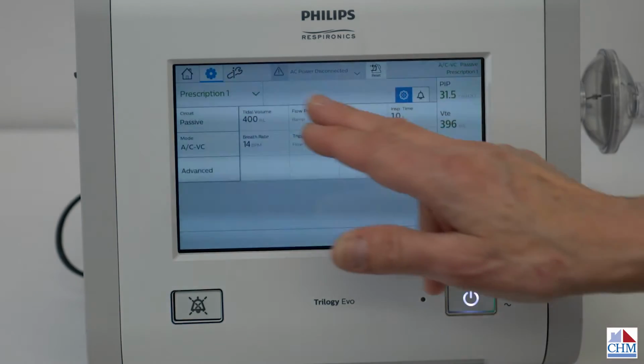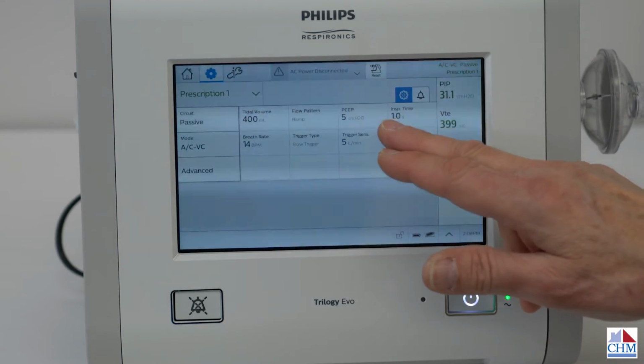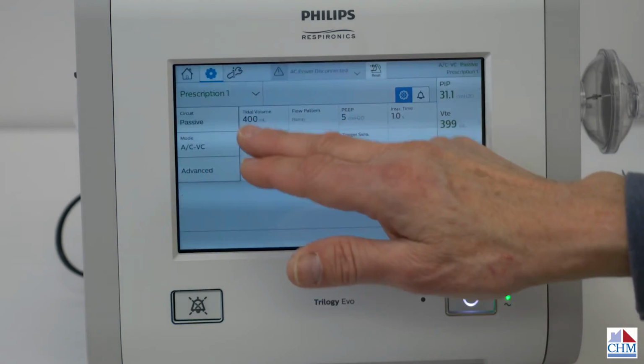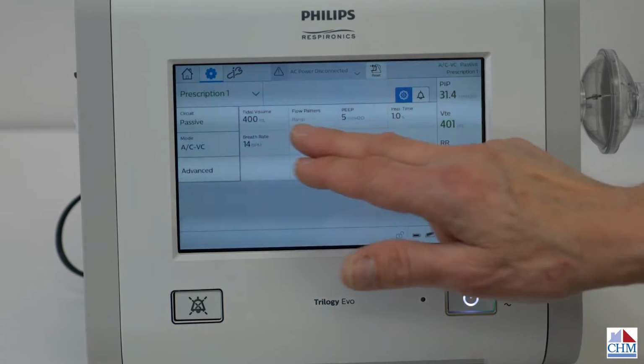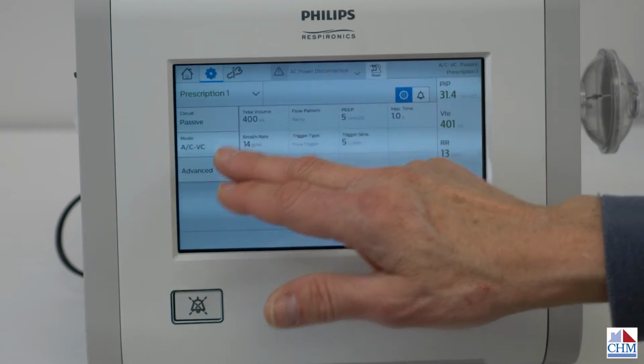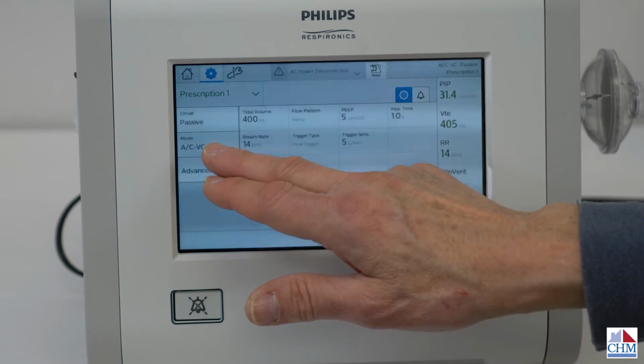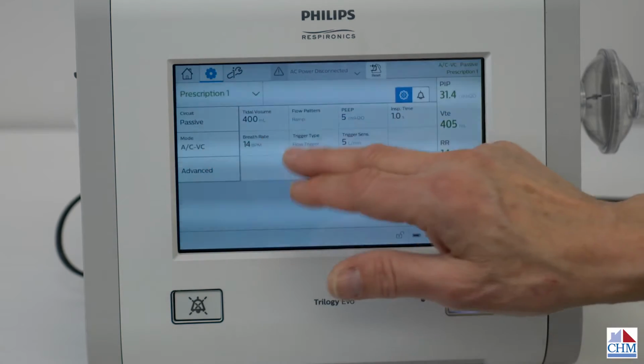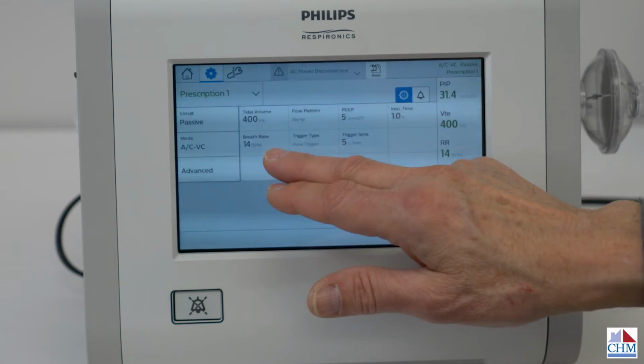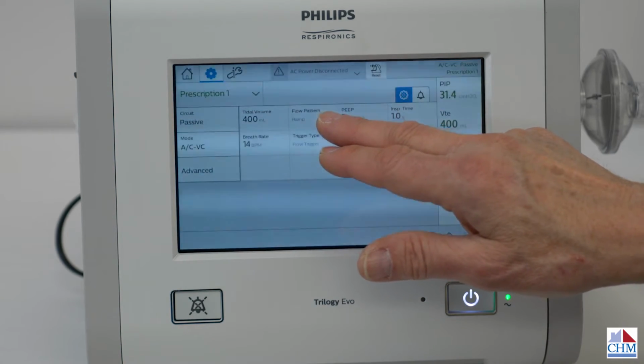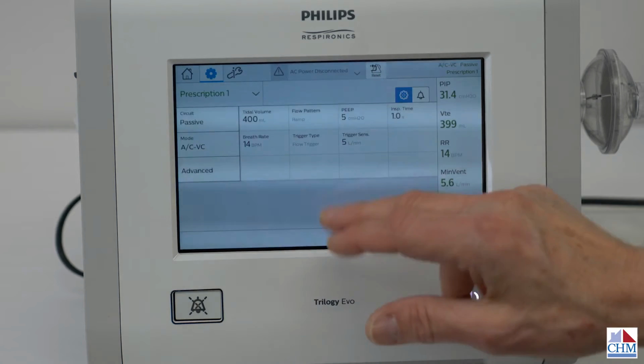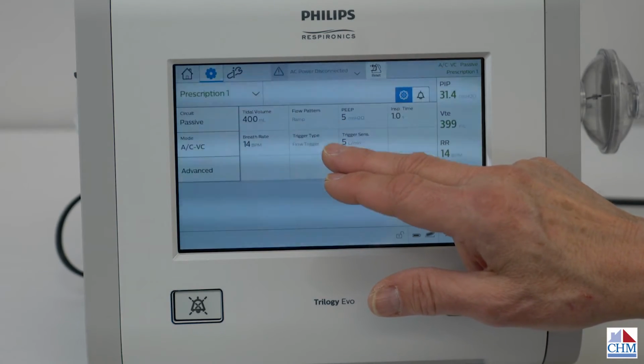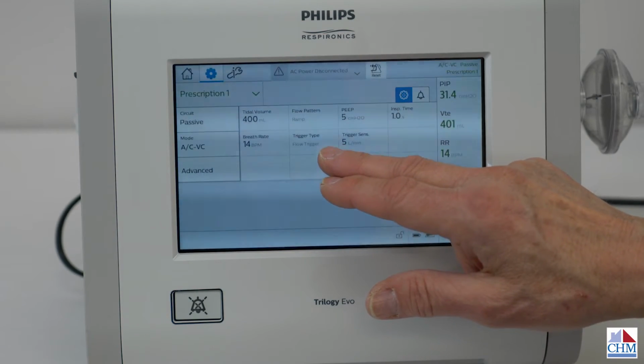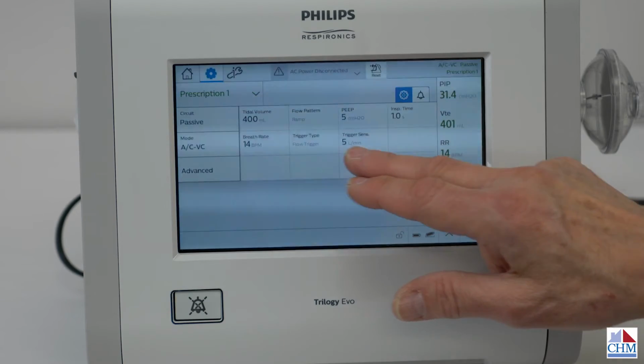So there's not a lot different. If you're familiar with the Trilogy, these settings are going to be very familiar to you. So right now we're in the assist control mode, volume, and we've got a volume displayed here, respiratory rate, flow pattern, the ramp flow pattern. The trigger type right now is flow trigger, and that is set at 5.